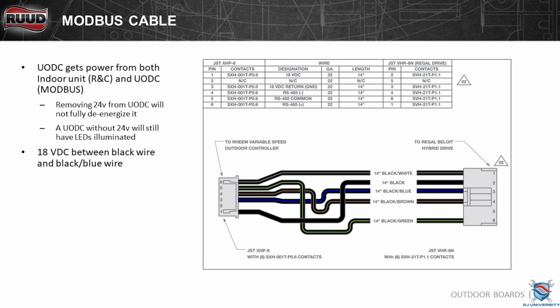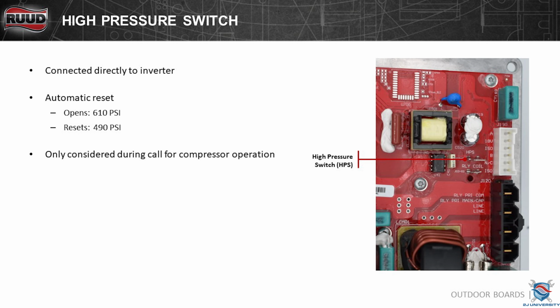R and C, you're going to have 24 volts AC on R and C. If you remove 24 volts from R and C, that does not necessarily mean that 24 volts is lost, because like I said, each individual component is giving voltage. Okay, so if you're trying to reset a code or something in a board, you need to disconnect high voltage and low voltage to get that to reset. High pressure switch opens at 610, resets at 490. And that's where you're going to find your high pressure switch on the control board.